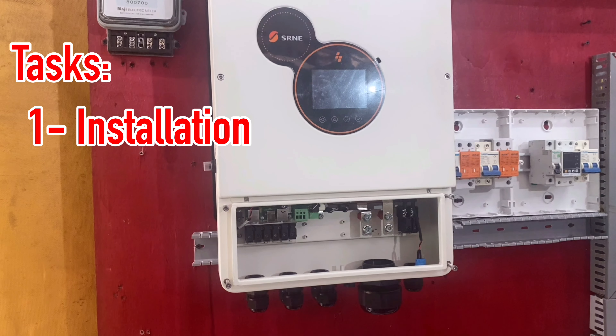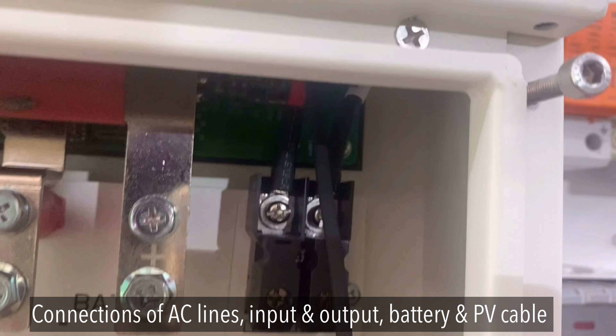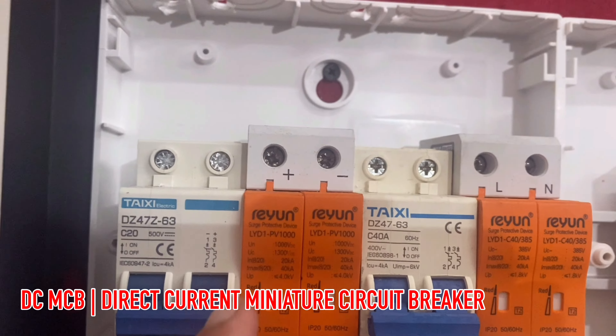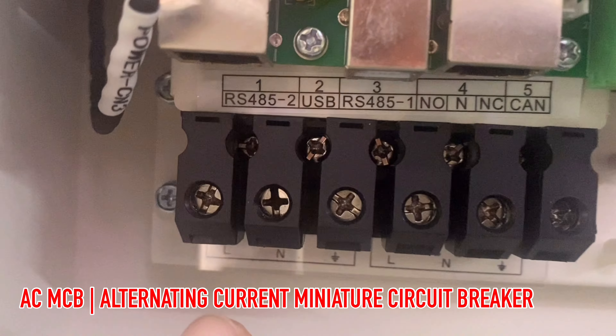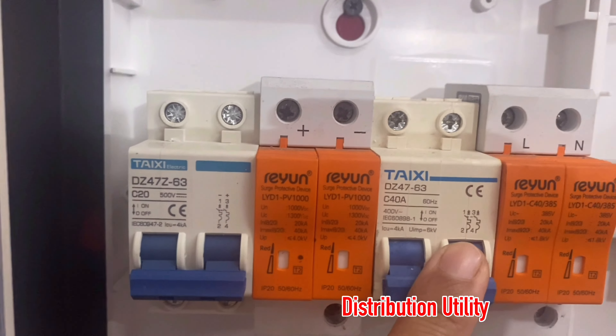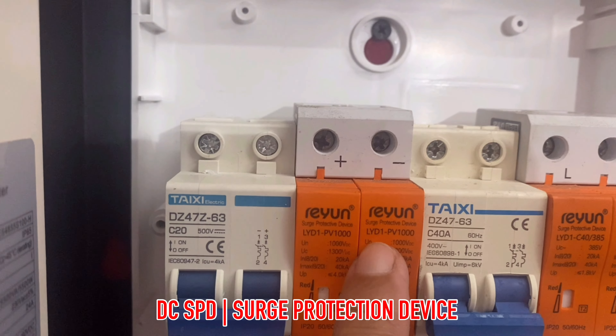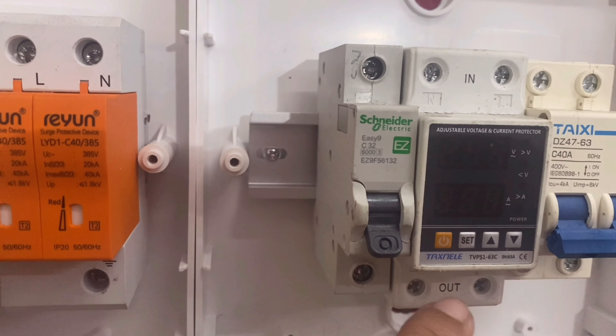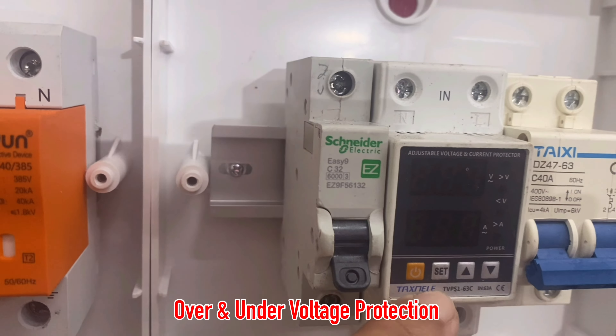First, I'm going to make connections of the AC line and AC out — line, neutral, and ground. We'll connect the grounds and use the 48-volt battery with the PV cable. We have here the AC MCB or miniature circuit breaker. This one is for the AC input coming from the distribution utility, and this one is for the DC surge protection device, and this one is for the AC surge protection device. I'll also be using some indicators — this is the over and under voltage protection — connected to this DC MCB.